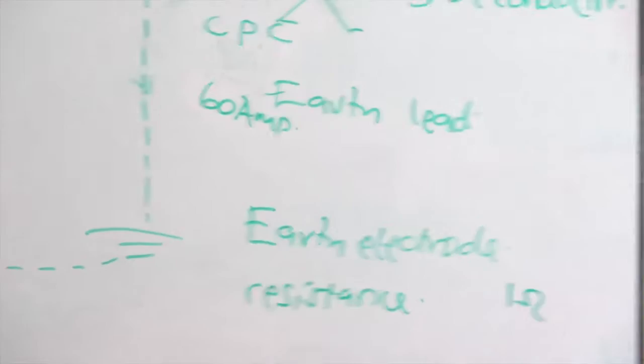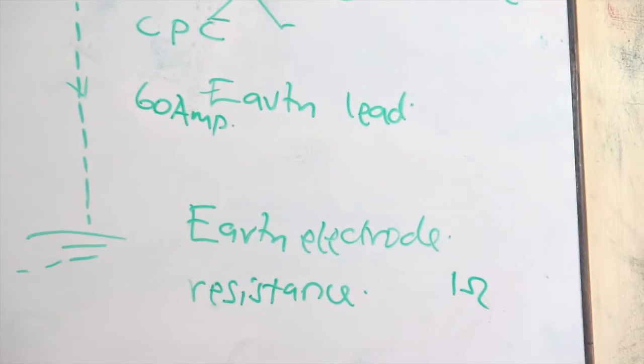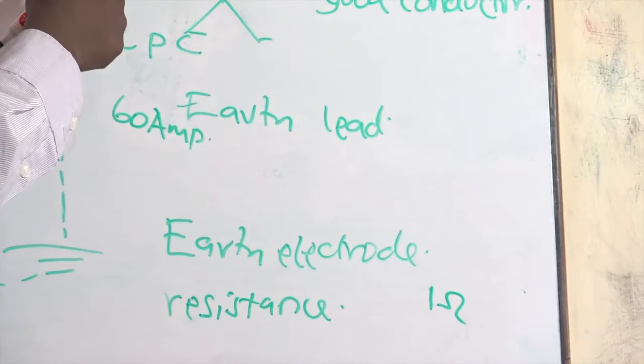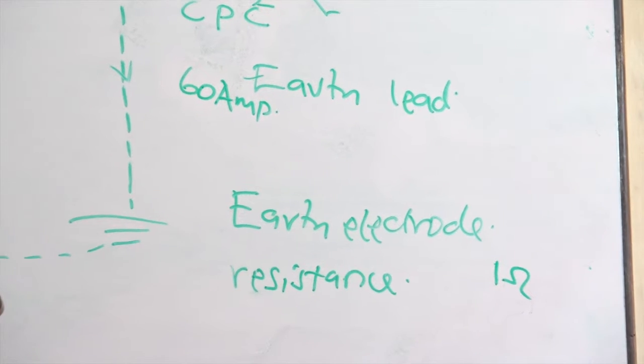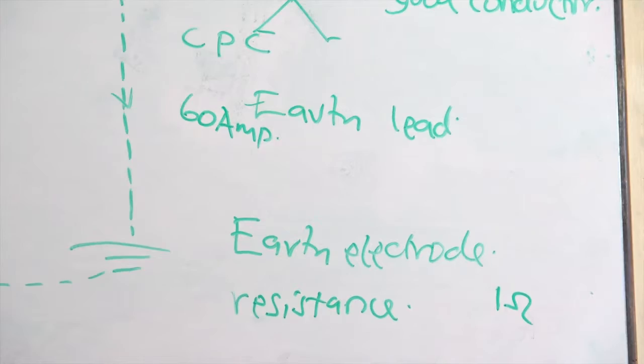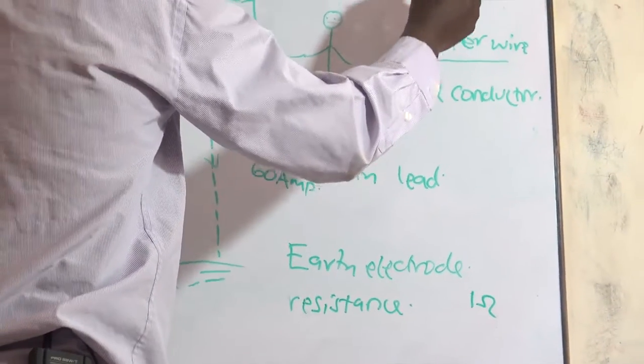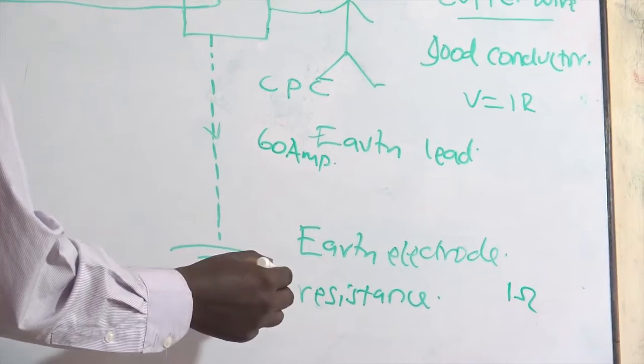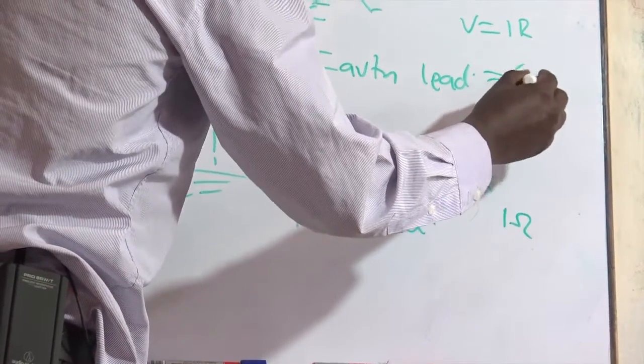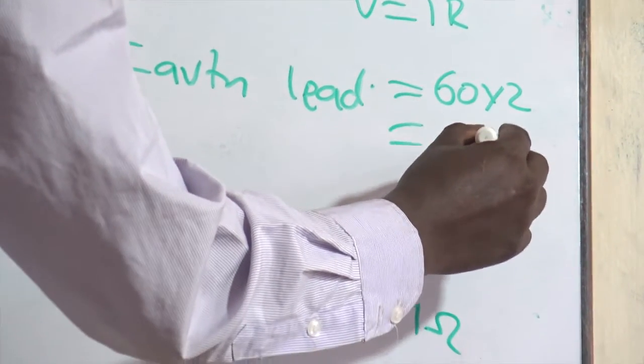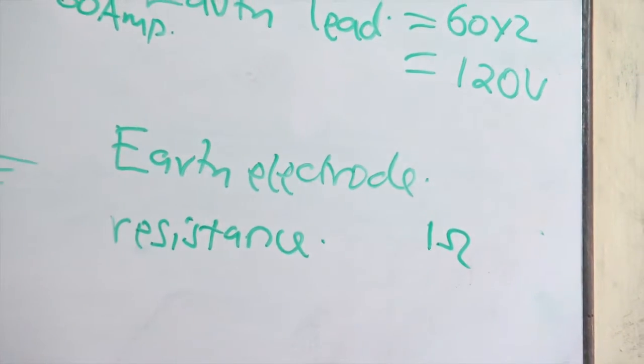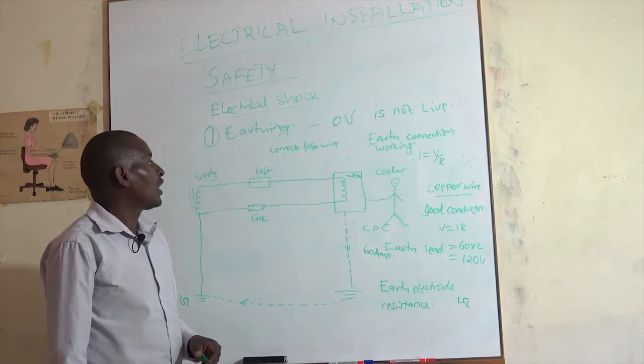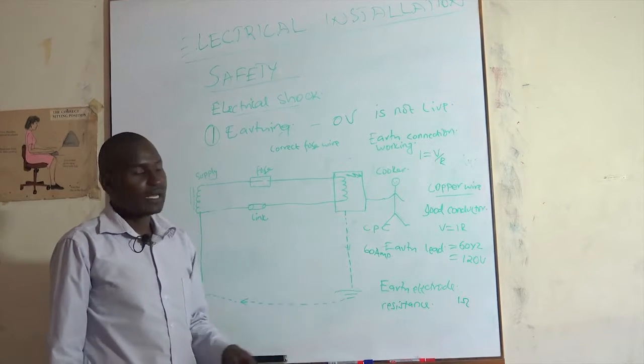and this one also has a resistance of 1 ohm, the total circuit will have 2 ohms. Now, the cooker that you are trying to protect, so as not to give an electric shock, will not be at zero potential, because we know from Ohm's law, I is equal to V over R. Now, V is given by IR. So if you have a current of 60 amperes times 2 ohms, you get 60 times 2, which gives you 120 volts. Now, this 120 volts will be the voltage at your metallic part, and this 120 can be dangerous.